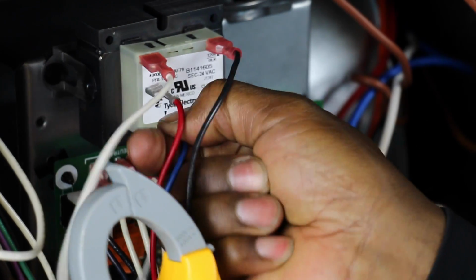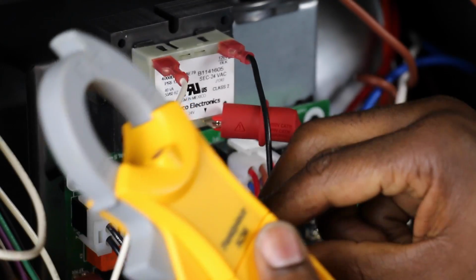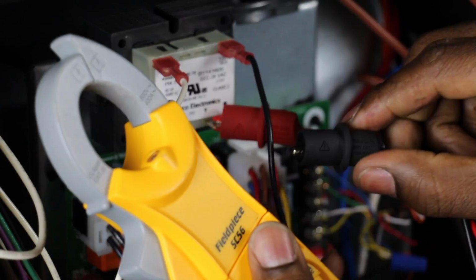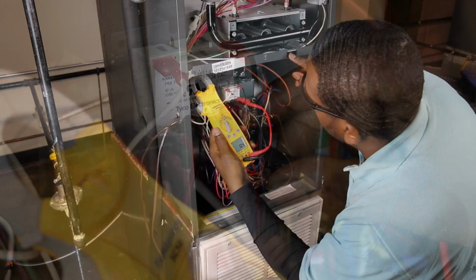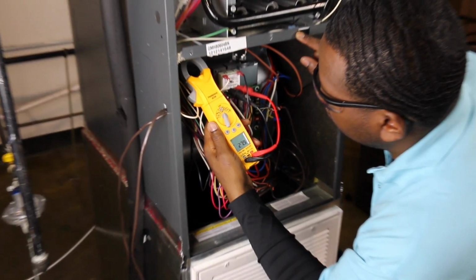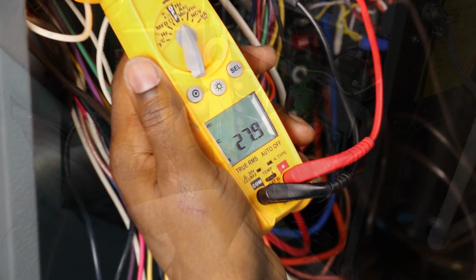By letting go of the door switch, the power is killed to the wires and Darren can plug it back up safely. Now he'll check for 24 volts present at the secondary side of the transformer. He applies power and has control voltage, a little higher than 24 volts.